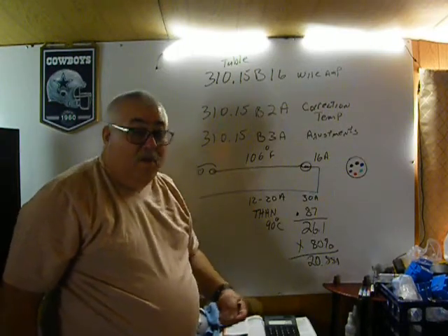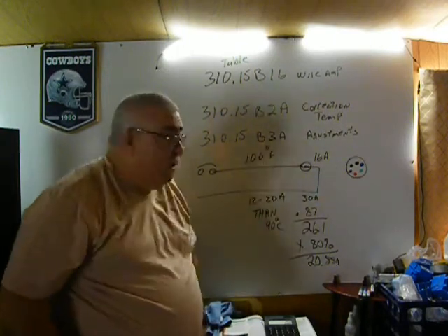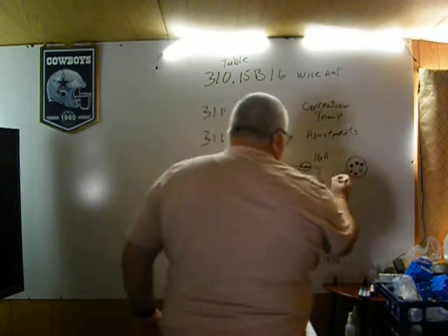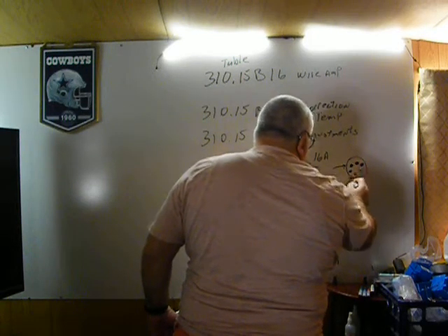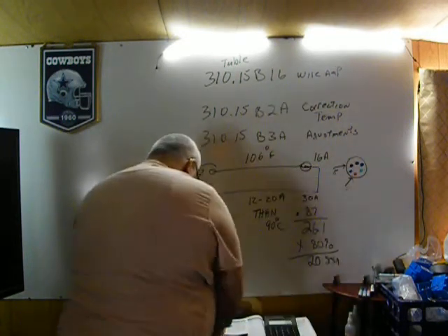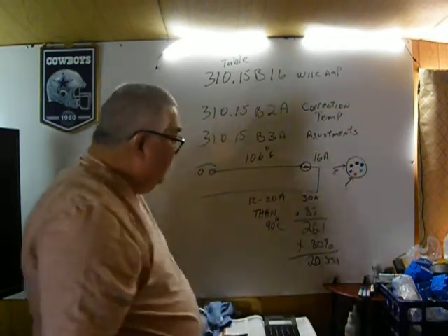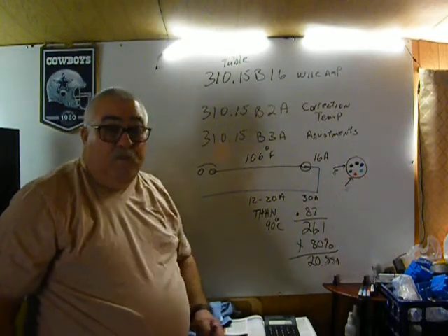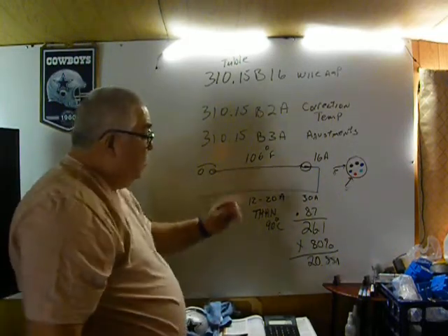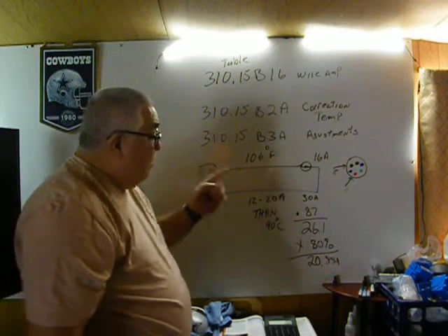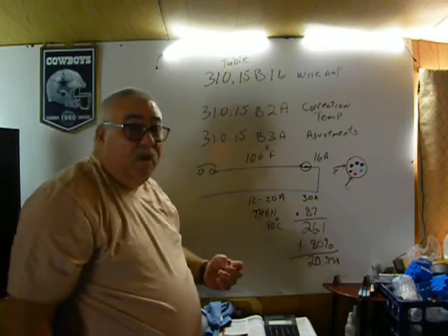If these wires were using 5 amps each, guess what, I could still use that 12 gauge wire. So in the figure that I showed, this had 5 amps, this had 5 amps, so my loads were balanced out and everything was okay. Okay, so I don't have anything on the neutral, so I don't have to count it.